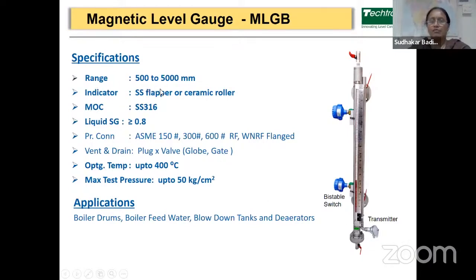The ranges are available from 500 to 5000 mm. Indicators are SS flapper or ceramic rollers. Material will be SS316. It is suitable for liquid specific gravity of 0.8 or greater than that. Then it is suitable for maximum temperature up to 400 degrees Celsius and pressure of 50 kg per centimeter square. So these are the applications, that is boiler drums, boiler feed waters, blow down tanks, and deaerators.